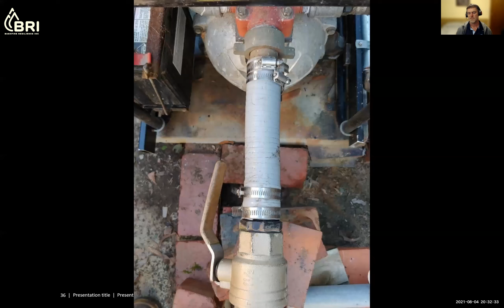The particular standpipes and the way they're protected is key — even the threaded fittings between them — you really have to focus on an all-metal approach. There are a few places where you have to compromise and potentially use flexible plastic pipe, and one of those is the entry and exit to the pump itself. Because the pump vibrates, if it's an internal combustion engine pump, there's quite a lot of vibration, and you can't really mount a hard metal connection to it — it'll eventually fatigue through and break, and it's not recommended in the installation instructions.